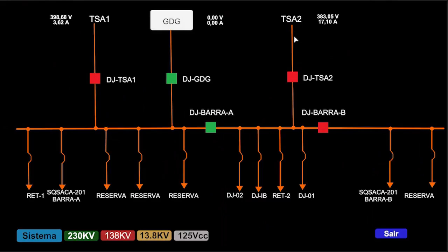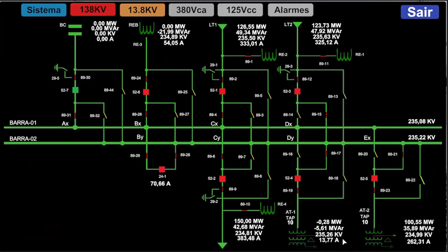This one, transformer 2, was left with the essential loads, and transformer 1 was left with the non-essential loads. So that's why the load is low. The load on the transformer. And then there's tap switching. All of that changes things. I'll give another example here.